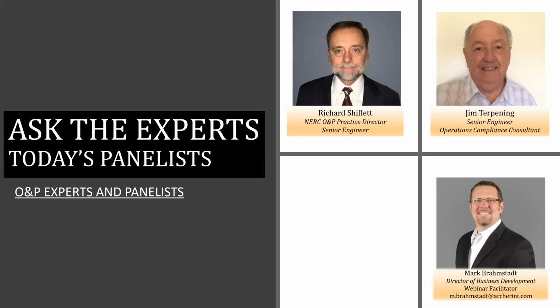Very good. Next question. For protection relays, may we exclude protection relay settings based on PRC 23 and PRC 25 compliance? Oh, yes. I've seen methodologies that leverage these two standards, but you have to be careful. For the audience's reference, PRC 23 is for transmission, although there can be generation applicability. Relay settings must be set according to PRC 23 if they have settings based on loadability. In other words, they could impact the system's ability to carry load.